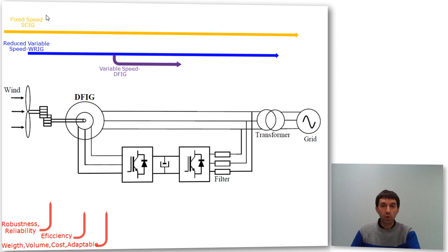So here we use a double-fed induction generator with a power electronic converter of a small scale. More or less 30% of the power of the wind turbine goes through the power electronic converter, and the rest, 70%, goes directly to the grid. With this design, it becomes dominant during many years, even decades, more than 10 years, and we obtain variable speed. However, depending on the locations, these wind turbine topologies were still being installed.